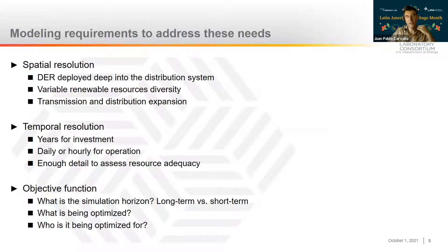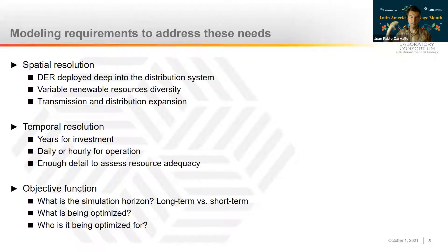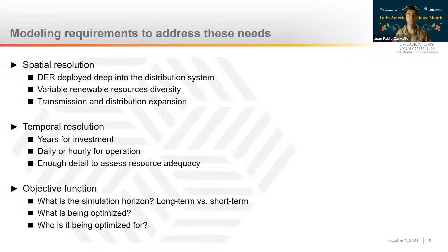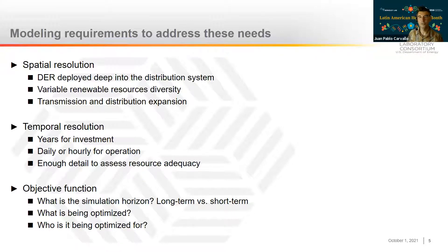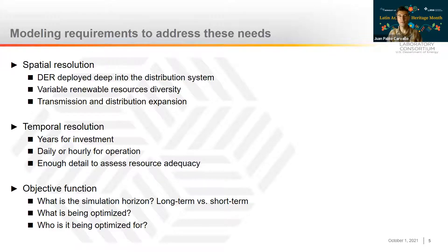As we move forward with analyzing distributed resources — particularly those of a renewable nature like solar PV — there are spatial and temporal resolution aspects that become increasingly important. Spatially, as was shown very clearly, the distribution system is massive and vast. DERs are typically deployed deep into distribution systems, so to understand their impacts clearly, models need enough spatial resolution to identify almost at the customer level, or at least at the transformer level, what's going on. It's important to represent resource diversity — if you aggregate spatial geographic zones, you lose substantial resource diversity that can come up due to shading or particular intra-urban radiation patterns.